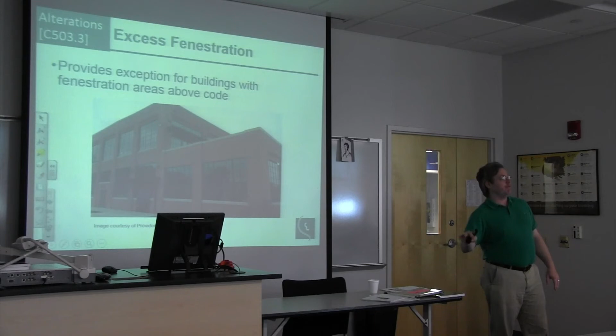Questions about alterations and additions. The question was, if we relocate 7% of the lighting fixtures and replace 2% of the fixtures without increasing load, are we within the allowable limits for Chapter 5, which covers alterations? The answer is yes. Relocating doesn't count as an alteration, so we're only talking about 2%. If you replace less than 10%, then yes, you're following Chapter 5.